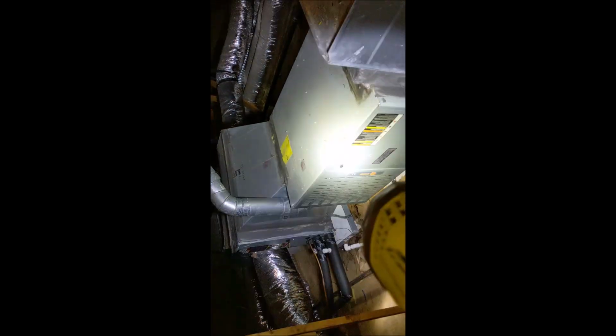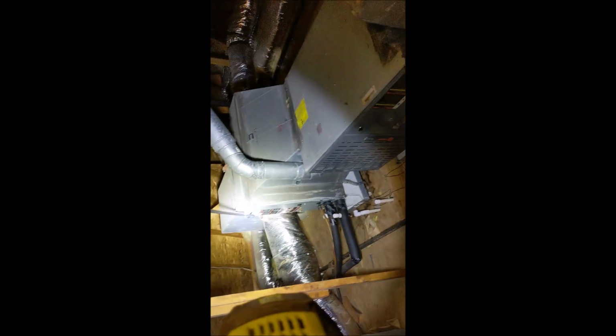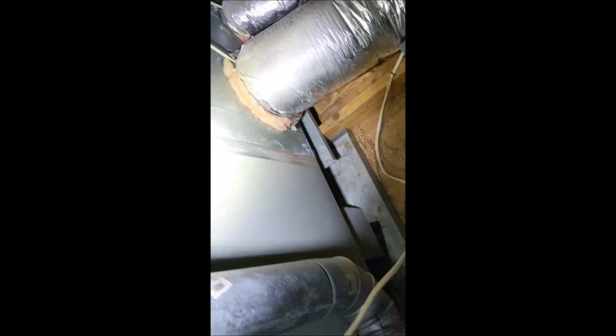All right, now we're on the other side of the evaporator coil. So what we have here is the air return. This is the air being drawn up from inside the house where the filter goes down there in the wall. And then we have a gas furnace, then we have a transom, or a little plenum transition, goes to a flat coil, goes to the supply air, and gets distributed amongst the registers. Same thing here, we got this gas furnace backing up to the air return. We got an A coil here, which is an encasing and a metal supply. You're always going to have a little suspected mold growth here. We always recommend air sealing that.